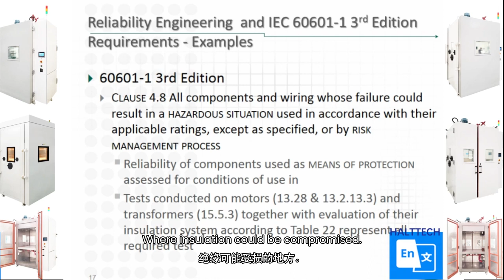Other examples. Clause 4.8 talks about components and wiring, and specifically looking at those components where a failure would result in a hazardous situation. This might be from exceeding their applicable ratings. It might be from several different areas. Specifically, that clause talks about the reliability of components used as a means of protection, and that we need to understand the reliability of those components. Let me give you an example of what I mean. If we have a device whose safe operation depends on the function of a part or a subsystem, we are required to know the reliability of those parts. We are required to ensure that they have been tested and assessed to meet the conditions that they will be used in. 60601 specifically talks about some types of components, motors, transformers, etc., where insulation could be compromised.